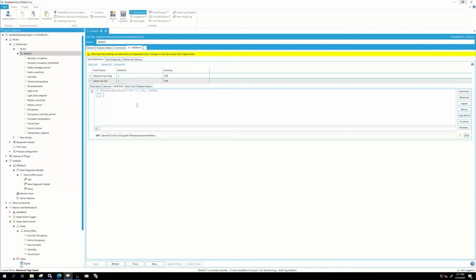The other nice thing about FDDWorks is that you can define a cost of a fault. I don't have one here, but the cost of a fault can be defined as, for example, how much energy it is wasting. If that fault is active for 20 minutes, maybe you're wasting 3 kilowatts of energy. Or if the fault is around for 1 day, the cost is expressed in the number of user complaints that you're going to get. So there are many different ways to calculate and represent faults, but ultimately the operator wants a dashboard that shows them what types of problems exist and potentially recommends what to do about it.